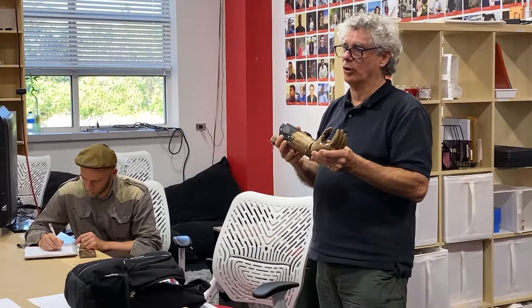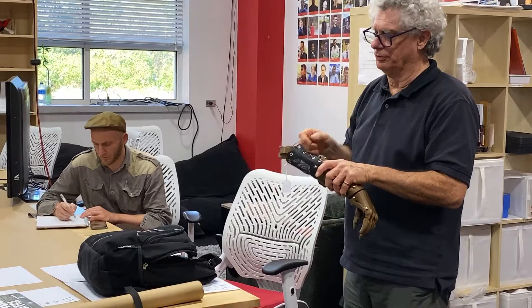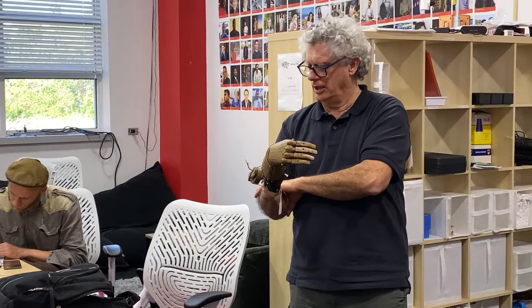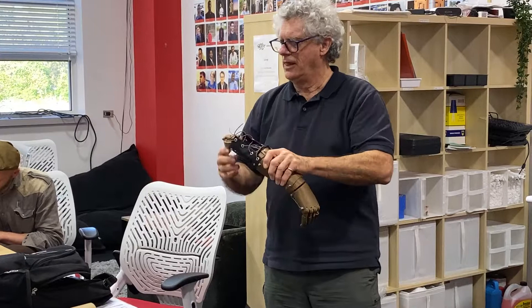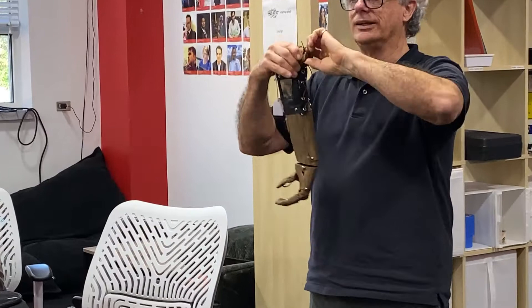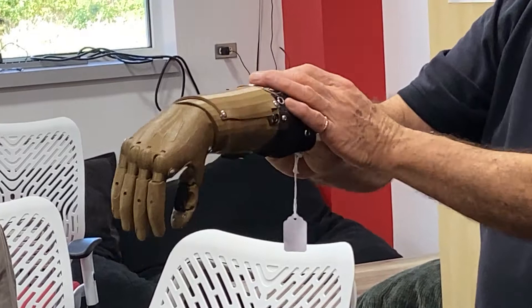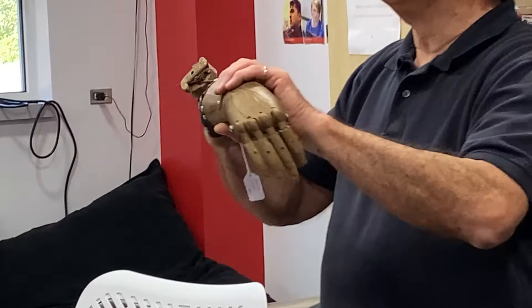This gauntlet setup actually has flexible filament in here — flexible battens, you might say. This is just window screen material, a plastic one rather than a metal one. This can fit the upper arm on this particular person, and he has enough room for his whole arm. This is a ratchet that goes both ways, so you can tighten it down. It's fairly effective in holding something with not much effort. It's a little bulky, but it works. We've superseded it already — I haven't even fitted anyone with it — but it's an interesting design and it is effective.